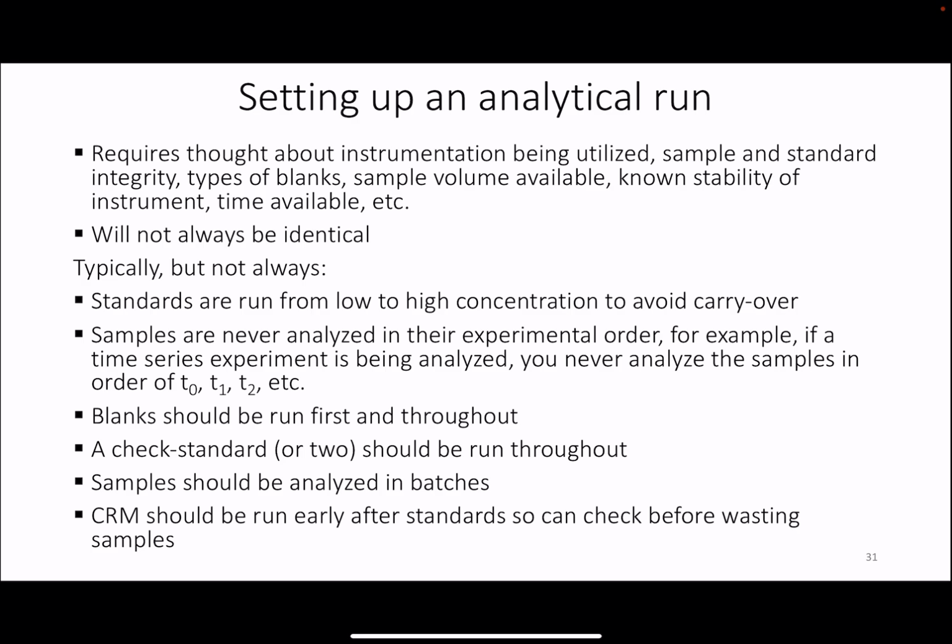Typically, but there can be exceptions, you run the standards in the order of lowest to highest to avoid carryover. It's also the fastest way to see if you're getting a linear response.